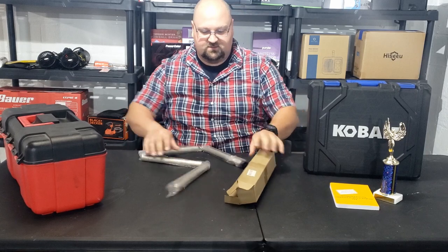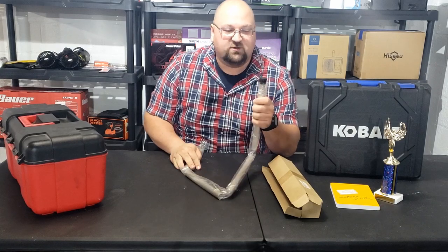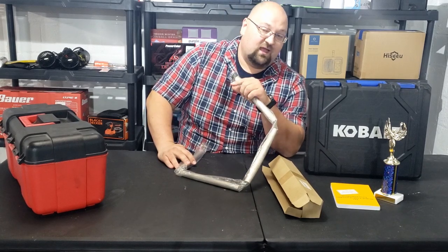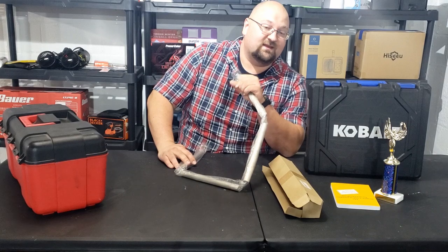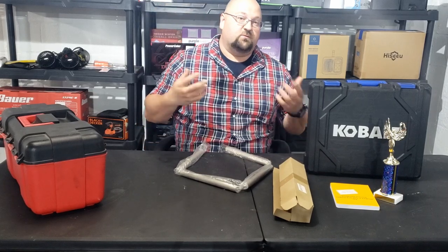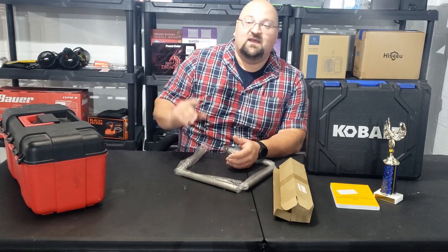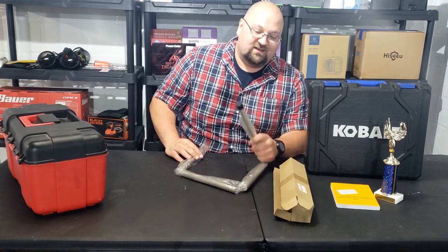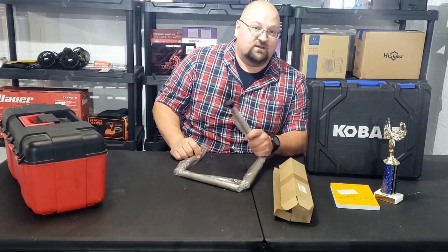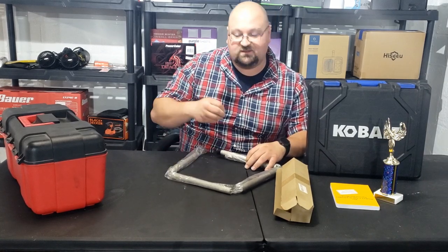That project being what looks to be the world's most lame version of nunchucks. This is actually the anode rod for my water heater. This is a flexible one so I don't have to tilt the water heater to get this in, and I'm going to use a hacksaw to get the old one out so I don't have to tilt it then either. Now the anode rod, for those of you who don't know, is a piece of sacrificial metal. Basically rust happens, your water heater is made out of metal, water is going through it, rust is going to break it. However, a little nifty piece of chemistry is that if in an enclosed system you have a metal that's more prone to rusting than other metal, that metal will rust before everything else, saving the other metal.